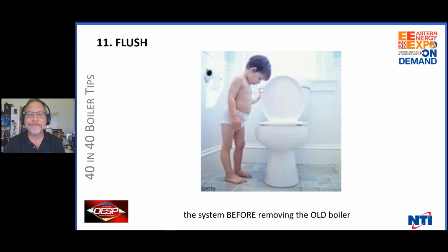Flush the system before you remove the old boiler. Get all that crap out of the system. I'll show you more later on this. But we all know that magnetite sits in wet legs of cast iron boilers. We all know it's just dead rust. We call it magnetite, iron oxide, whatever you want to call it. It's magnetic. It will kill boilers.